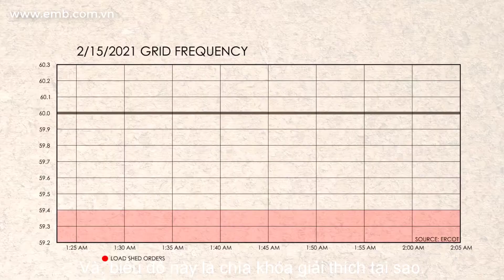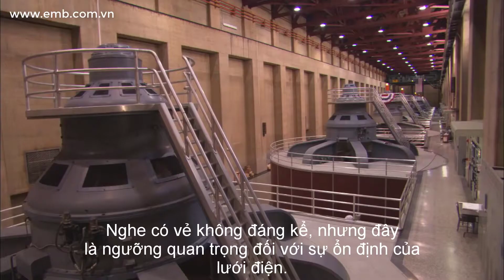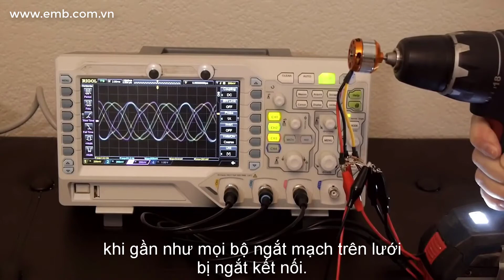Of course, in many places during the storm, that is not what happened, and this graph is the key to why. As more and more resources tripped offline so quickly, the frequency of the Texas power grid began to drop. ERCOT continued ordering additional load to be shed from the system, trying to keep up with both the rising demand from the cold weather and the quickly failing power plants. At about 1:50 a.m., the frequency fell below 59.4 Hz. It doesn't sound that significant, but this is a critical threshold for grid stability. Power plant controls are set to automatically disconnect if the frequency stays below 59.4 Hz for more than 9 minutes. In such a situation, as each generator trips, the frequency would quickly plummet until just about every circuit breaker on the grid had disconnected. 4 minutes and 37 seconds is all that separated Texas from a complete grid collapse.